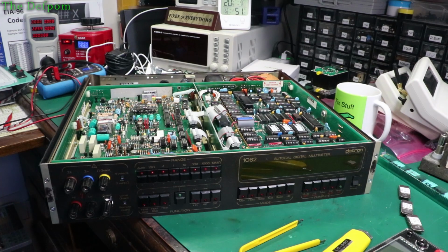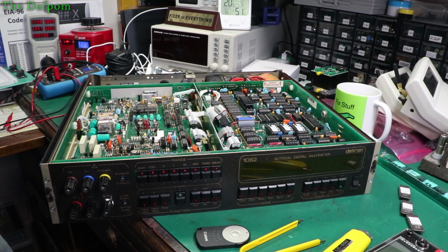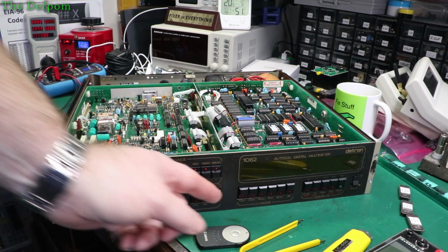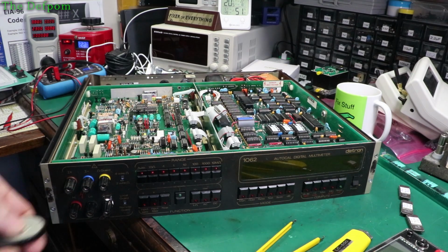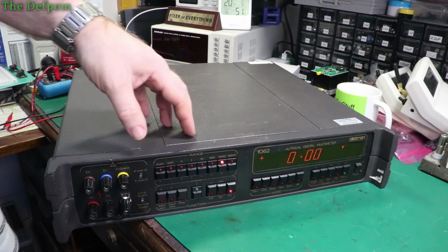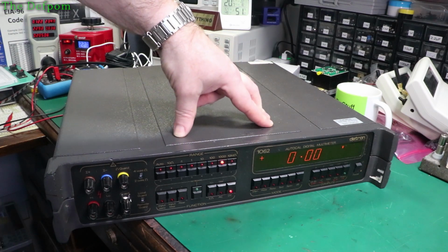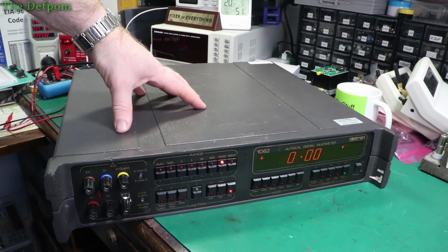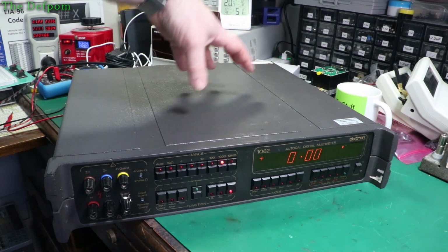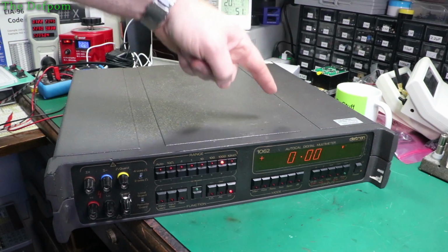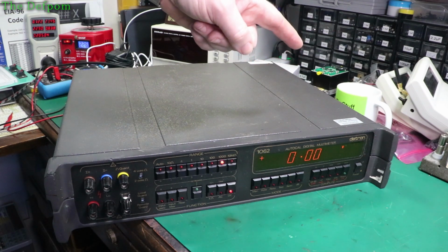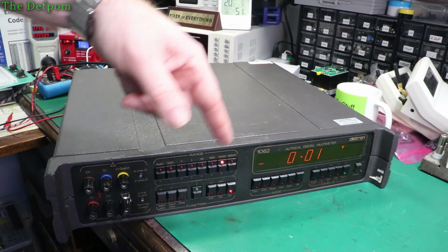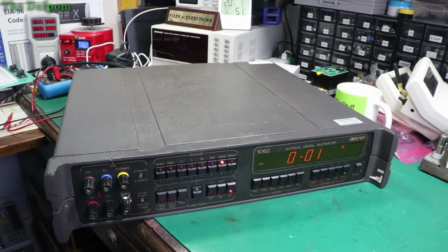It's also possible that part of the problem is that the unit's not warmed up. It's still basically cold. So what I might do is power it up for a little while, put the covers on, give it 10 minutes to settle, and then redo that test and see if it still fails. If it does, I might have to relook at those calibration values. Actually, I don't think I've done the ohms board calibration on this thing. I've done the analog board calibration, I've done the AC board calibration, but I don't think I've done the ohms board calibration. That might be why it's failing. I might have forgotten it.